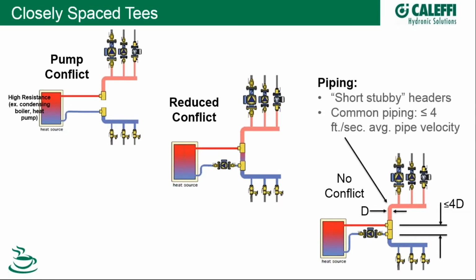So on your piping in your secondary, we call it short stubby headers. As close together as these pumps can be, the better, and to minimize the travel between your T here and your pump. Okay, short stubby. And then your common piping, that is the piping in your secondary that each of these pumps see, which would include from this point on your return all the way through back to here, you want to keep the flow rate such that your average pipe velocity is not much more than 4 feet per second. Doing so, you should be in pretty good shape altogether, minimizing any pump conflict.